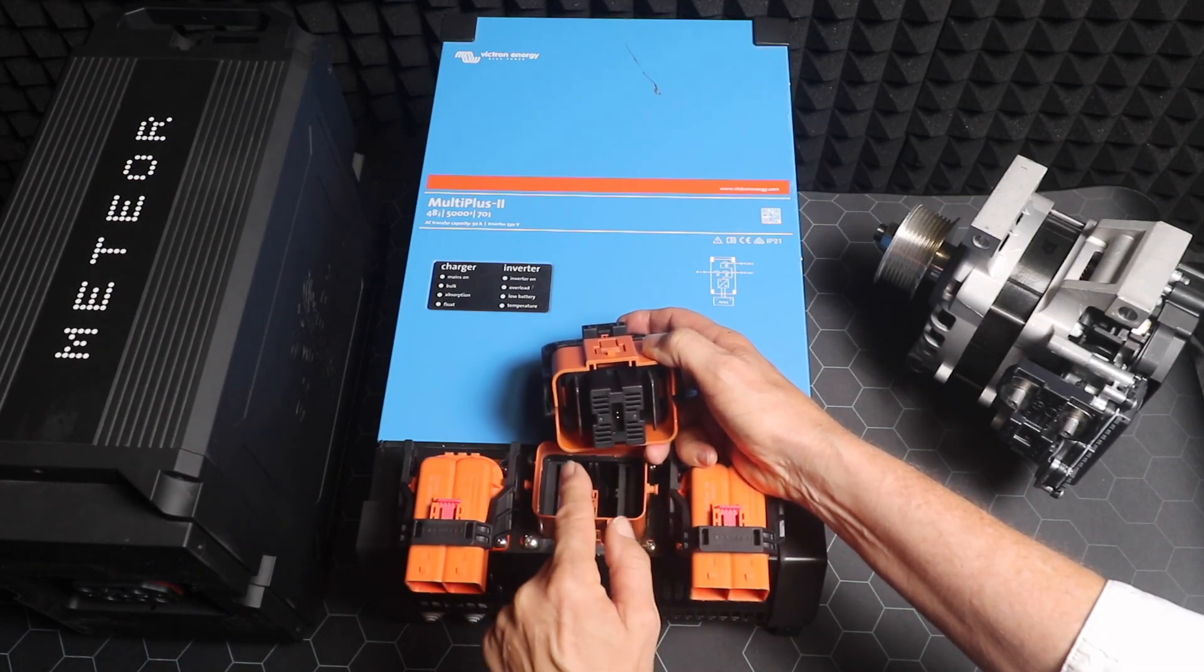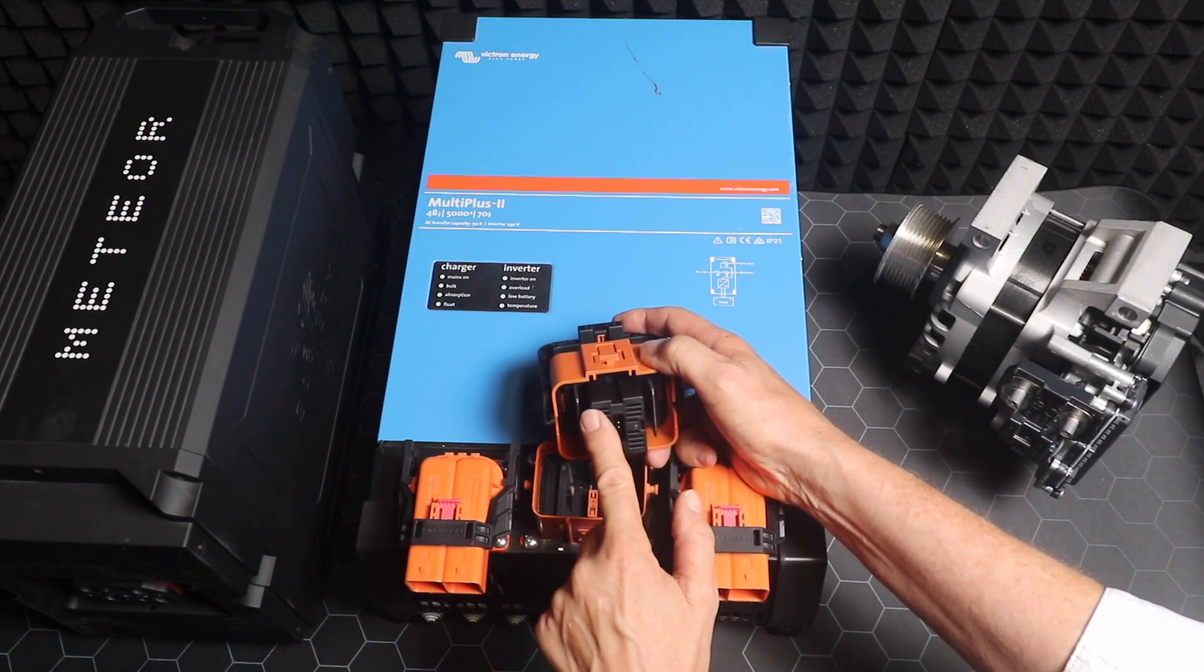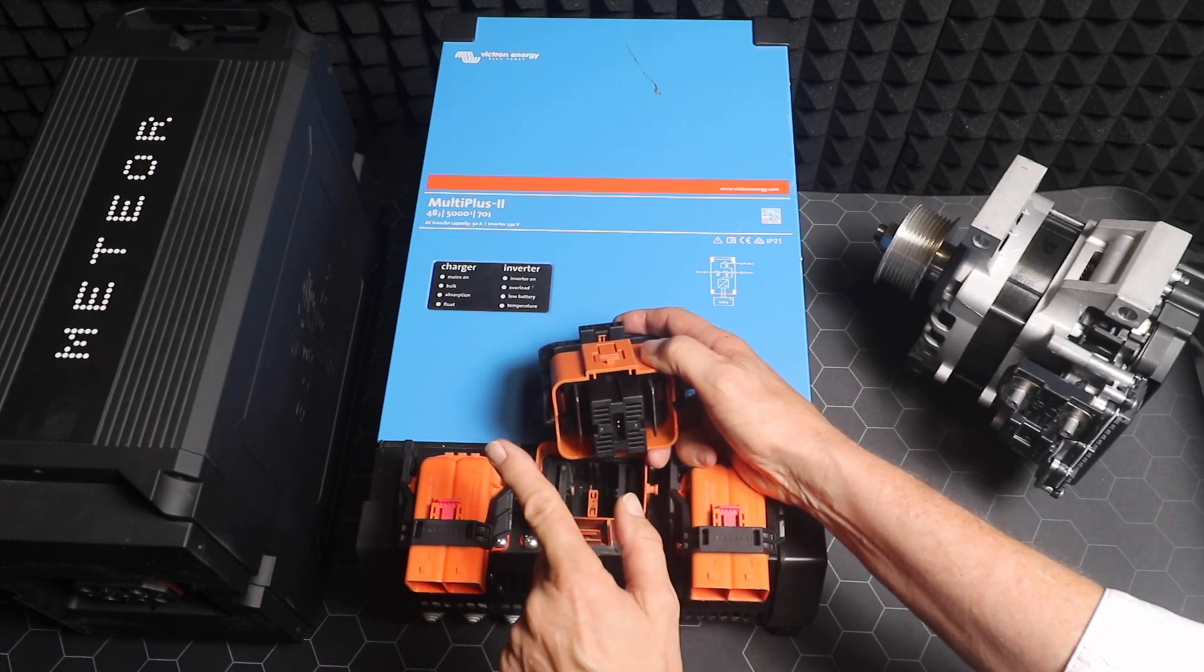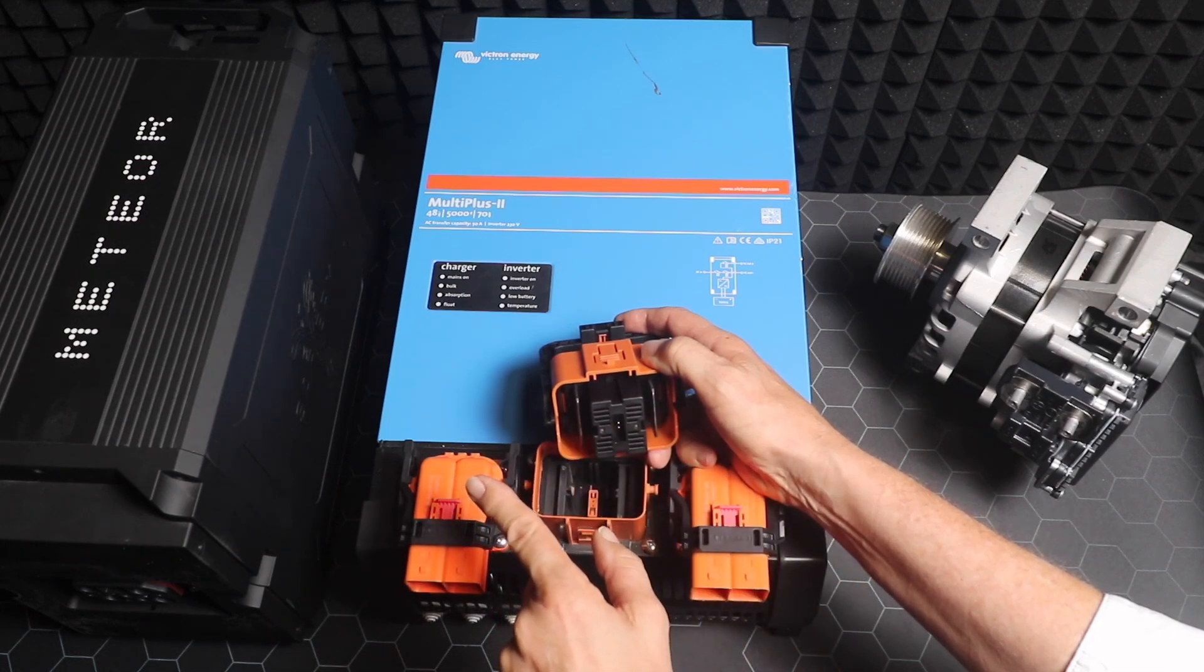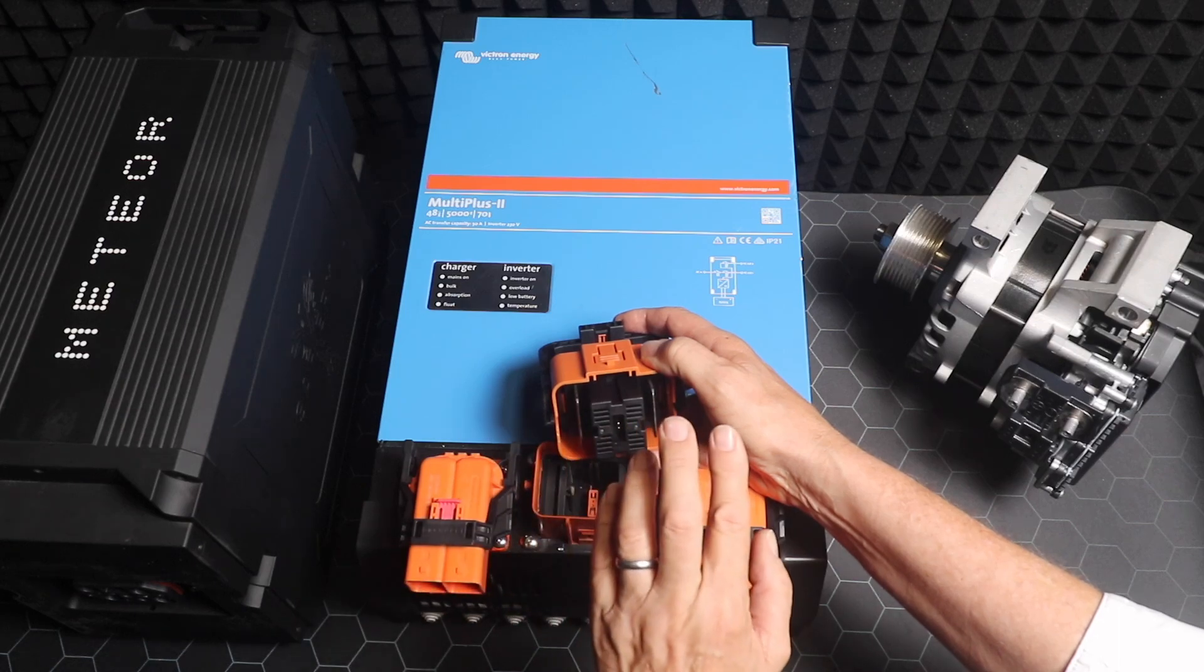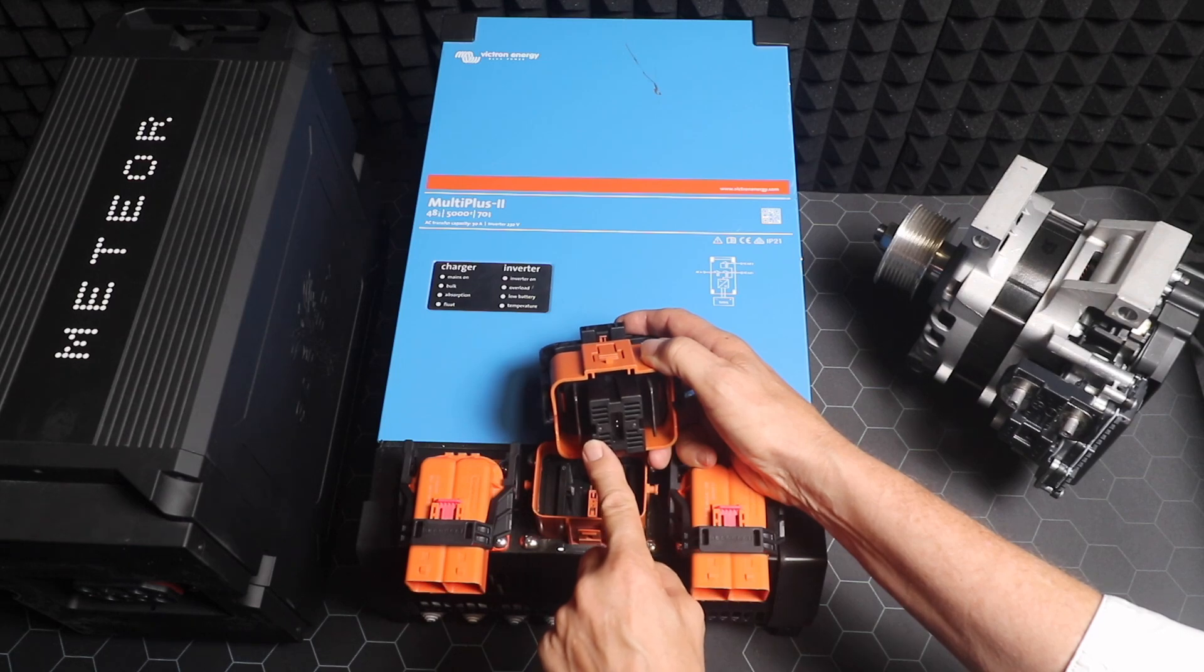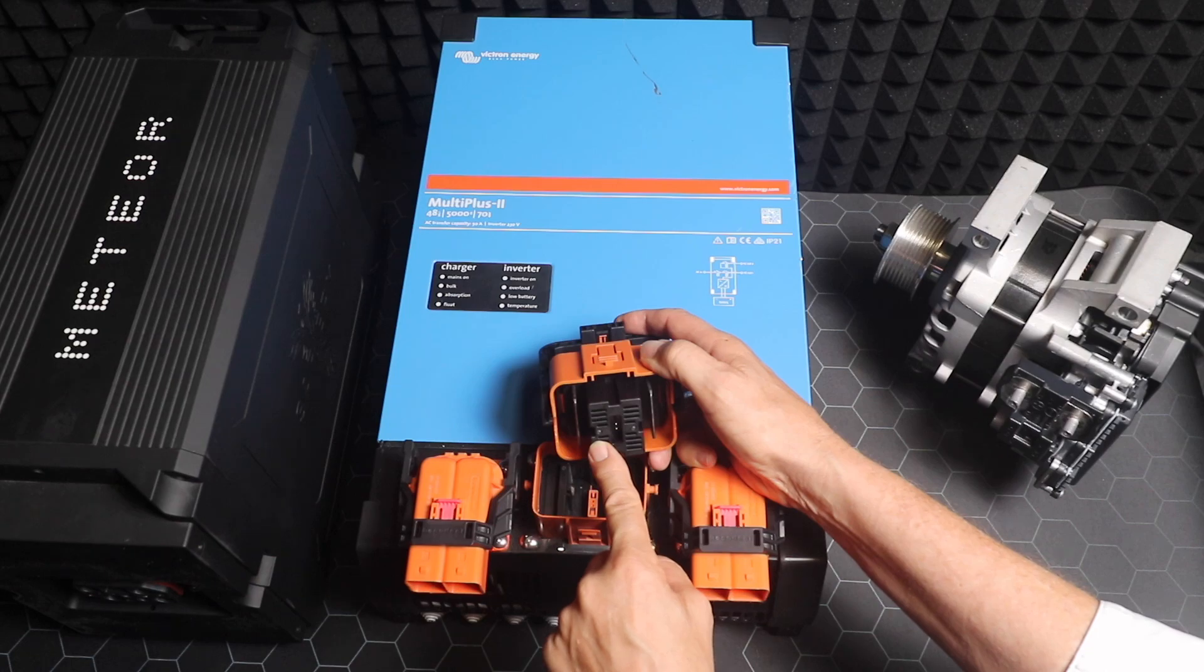This totally isolates it. That's the equivalent to the isolator. The fuse is this part in the middle here. It's not a normal fuse. We still have to have a fuse to protect the wire in both cases, and those normal fuses operate for the normal overload scenario. This fuse here will let those overloads go through, and this unit then on the dead short opens faster than a traditional fuse. That's why it's a different type of device.